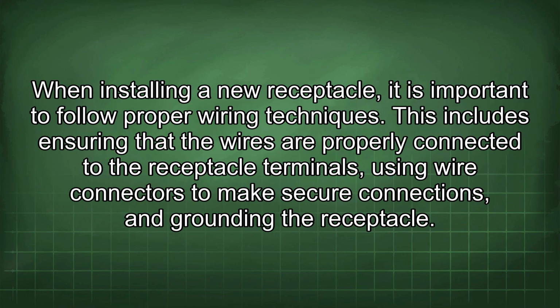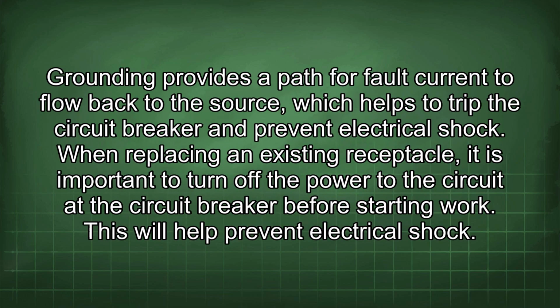When installing a new receptacle, it is important to follow proper wiring techniques. This includes ensuring that the wires are properly connected to the receptacle terminals, using wire connectors to make secure connections, and grounding the receptacle. Grounding provides a path for fault current to flow back to the source, which helps to trip the circuit breaker and prevent electrical shock.